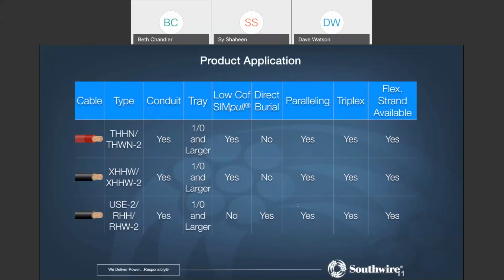And so, for example, if you're running 3 500 kcmil conductors and you need brown, orange, yellow for a 480 volt installation, then those conductors will be on the same reel and you would pull them side by side together, but they are not twisted together or cabled together. They're simply in parallel with each other.